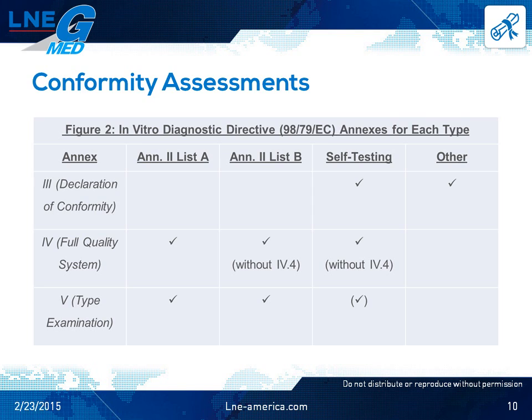On this slide are the conformity assessments that are required for in vitro diagnostic devices. Don't forget, IVDs have their own directive and their own classification system. With the new regulation that's coming out, the classification system is predicted to change. In the meantime, these are the conformity assessments that you can use when applying a CE marking to an IVD. As with the Medical Device Directive, the conformity assessments for IVDs are found in the annexes to the IVD directive.